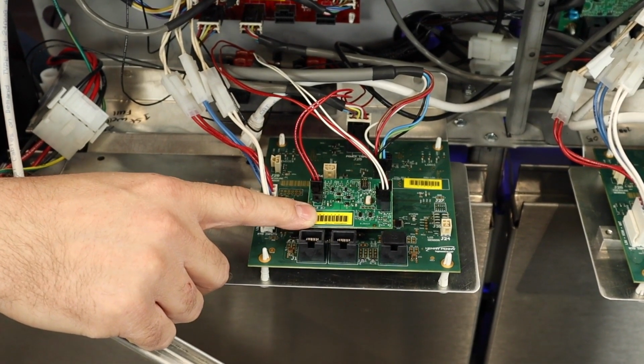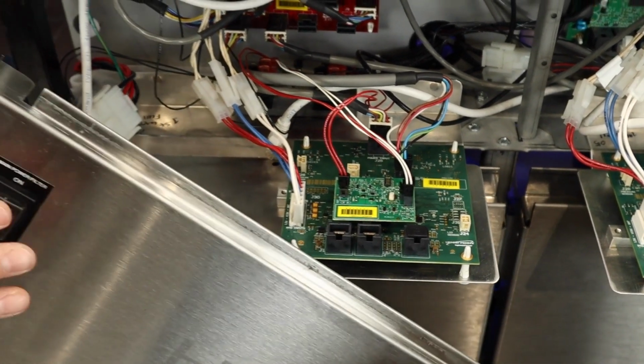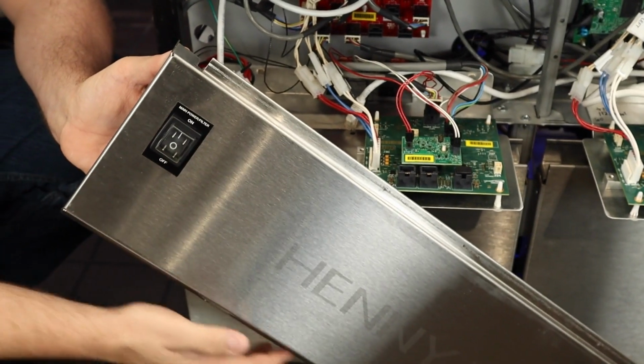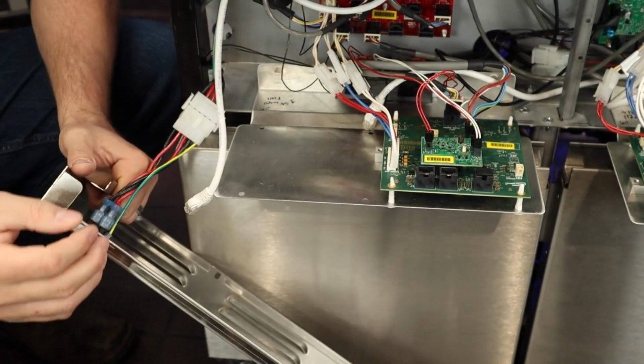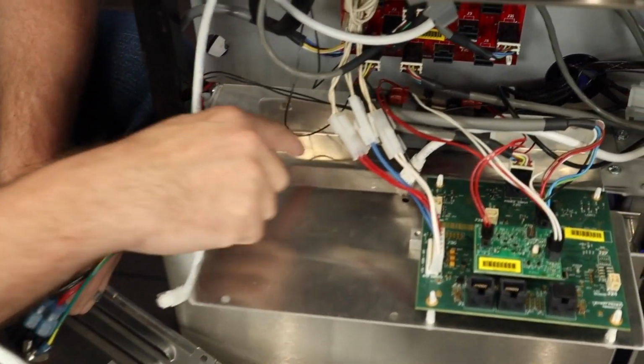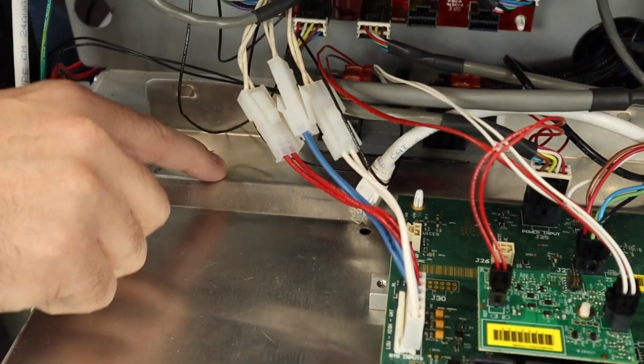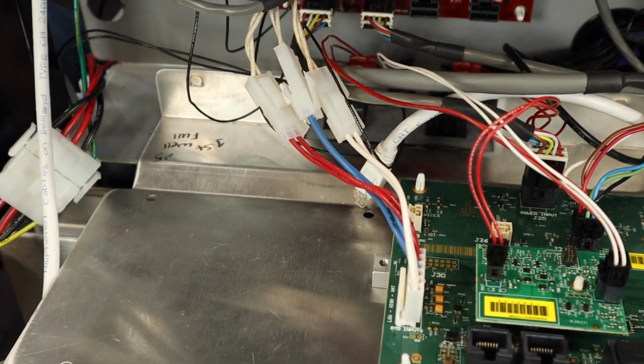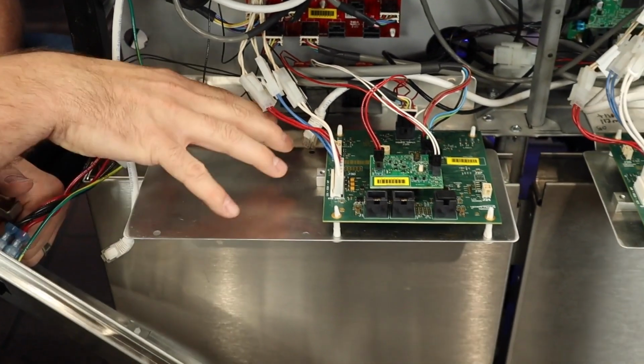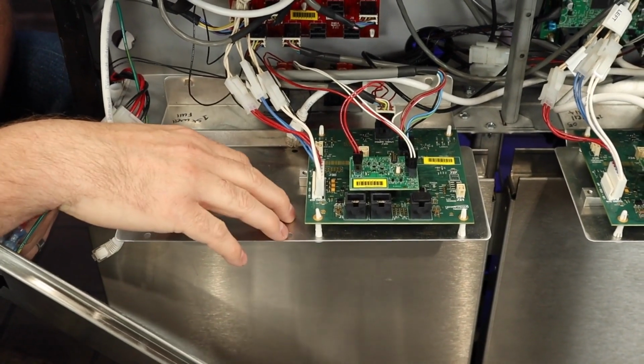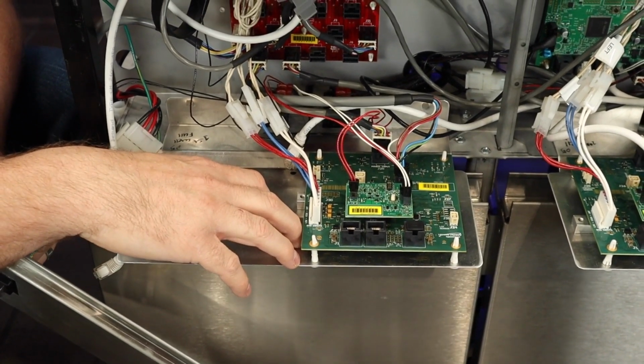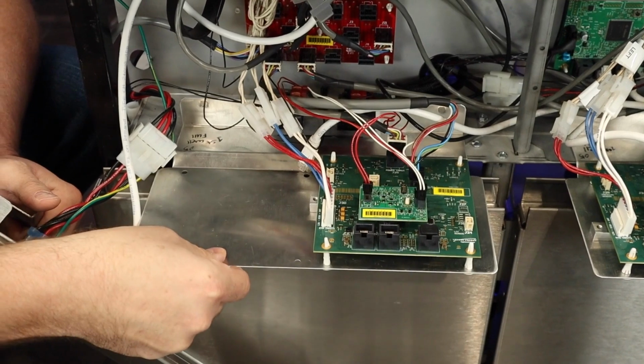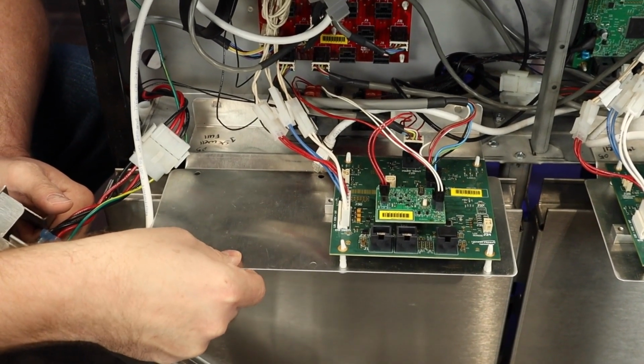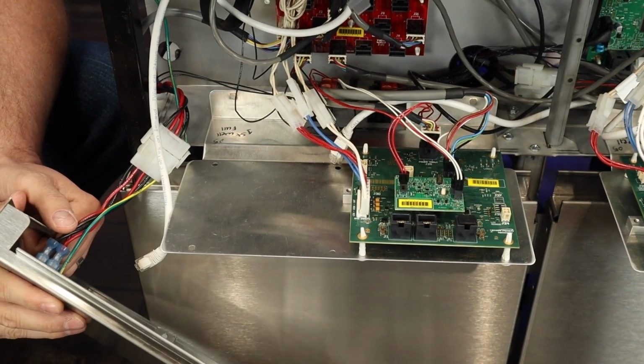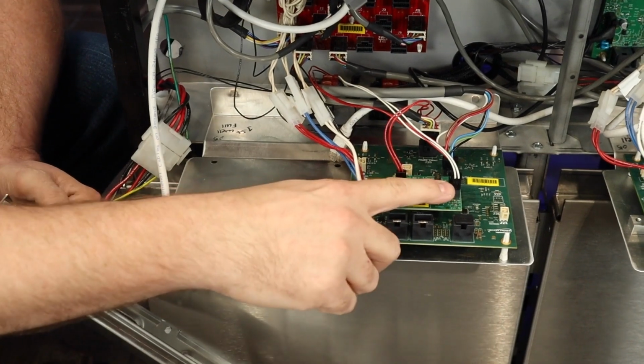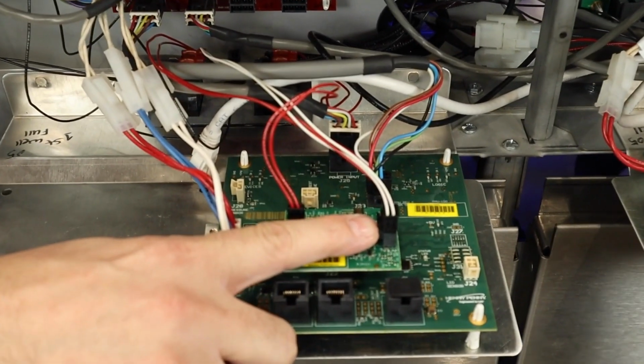If that is good, then we can remove our access panel here with the screws at the bottom of it, then remove the two 3/8 mounting nuts on our PMU mounting plates, and then we will have the PMU brought down so that we have access to our PMU board. It will sit stationary like this as I have it shown here so that you can work on it. Now we can check our actual high limit probe in question.